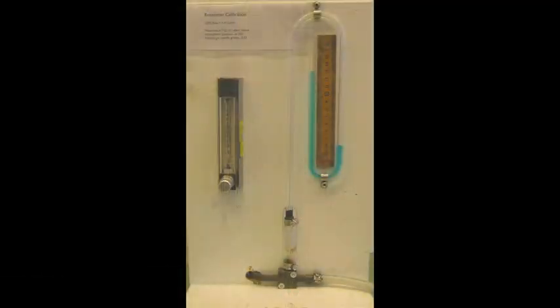This tells you the percent flow. The calibration is 100 percent flow is 4.41 liters per minute at 7.62 centimeters of water. You will need to adjust that.